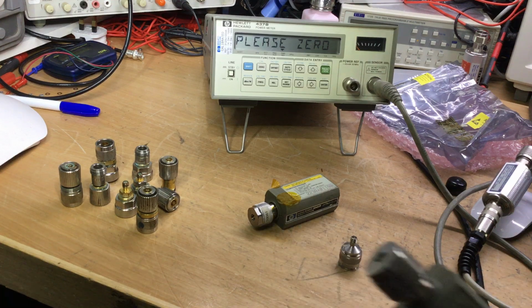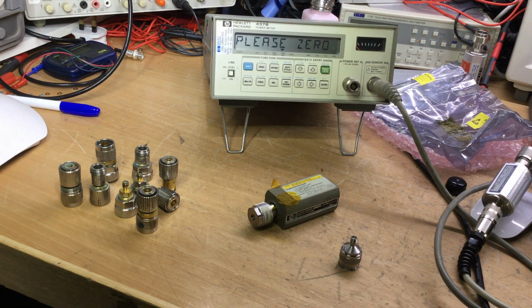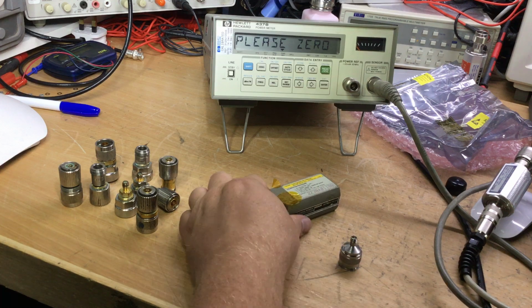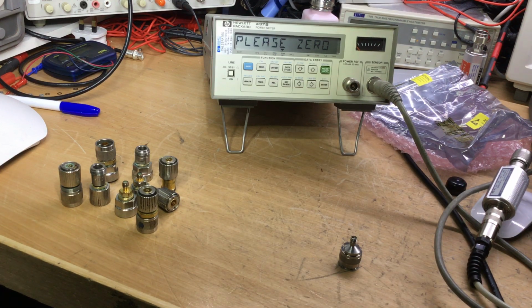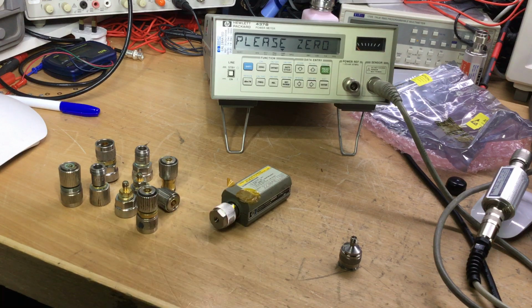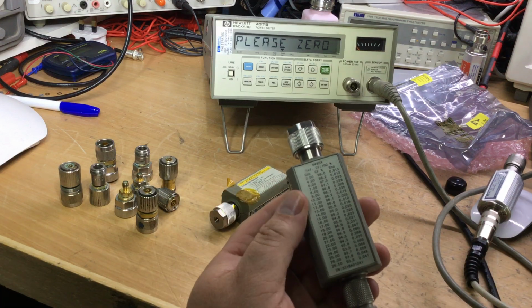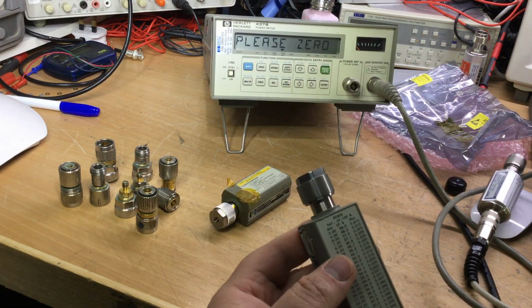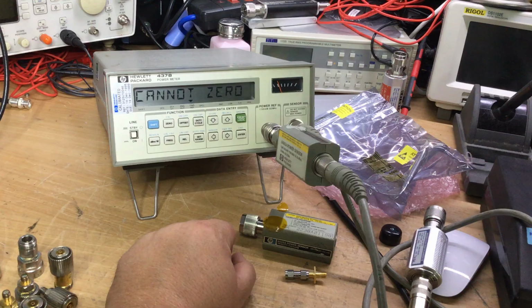Just have a look at the linearity factor on this. That's 100% as well, calibration factor rather. And then we've more or less, let's just check the frequency characteristics of this on the table versus the other. I doubt they'll be the same, but you never know. No, they're different obviously. I thought as much. So I'll have to enter in all this data now into the meter, which will take me quite some time to go through all that again, and then we'll come back and carry out the tests on this.